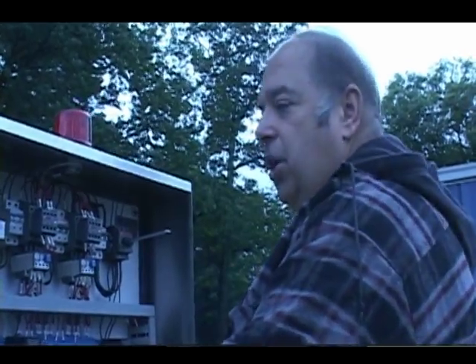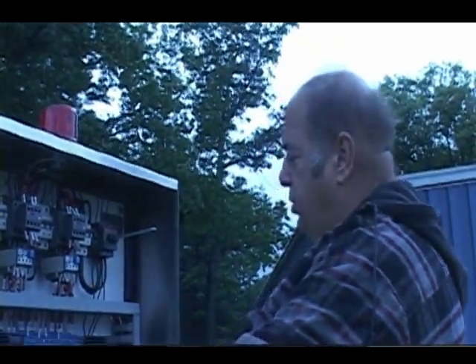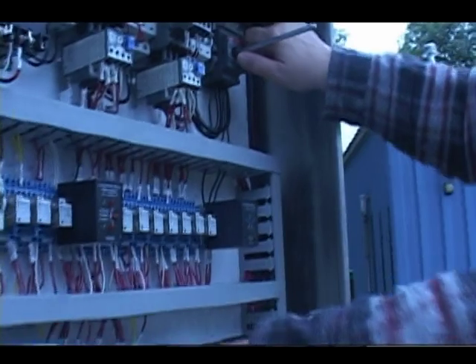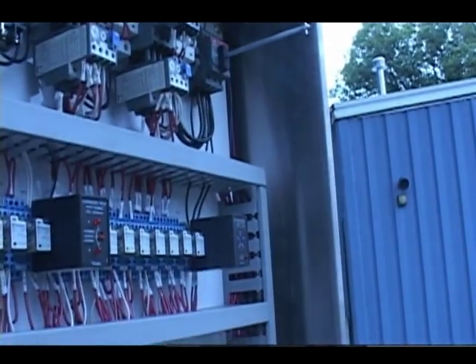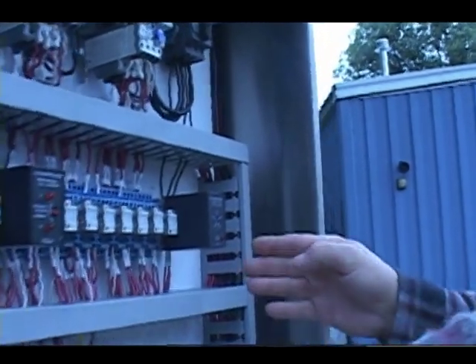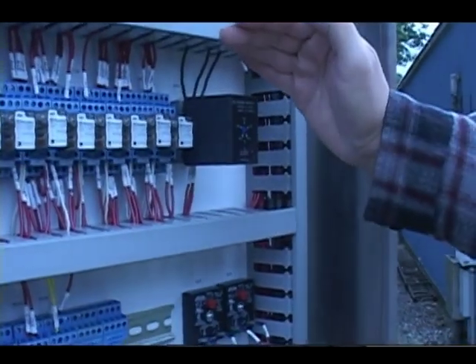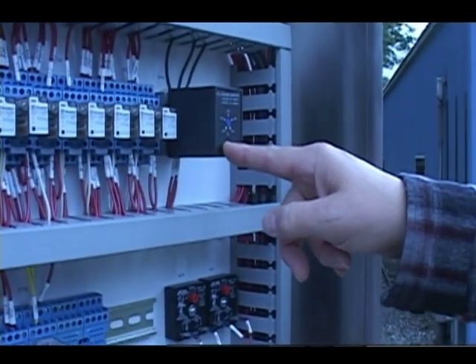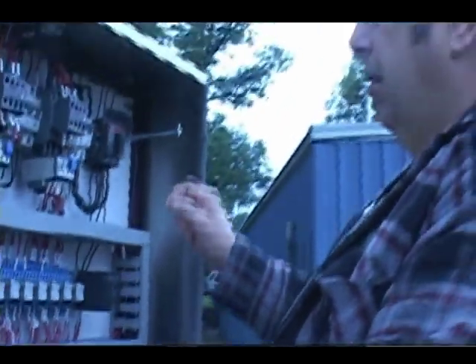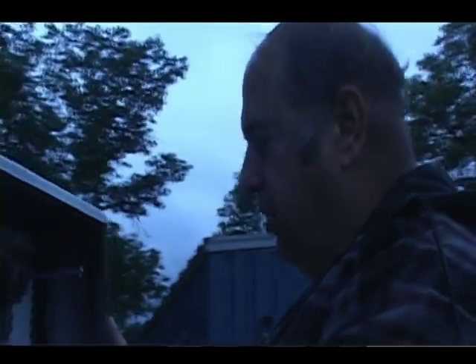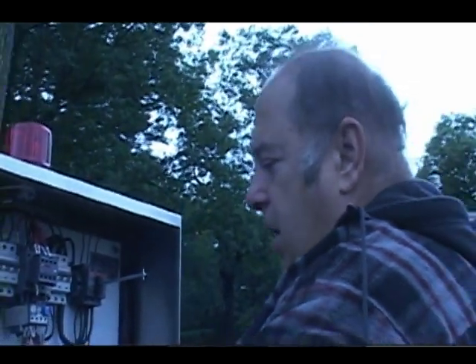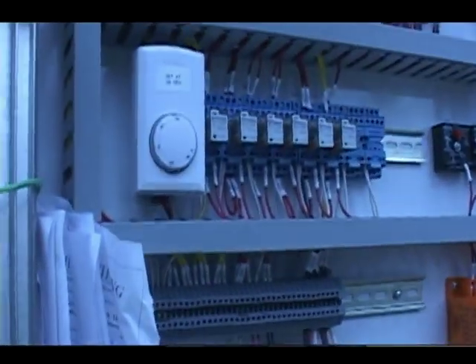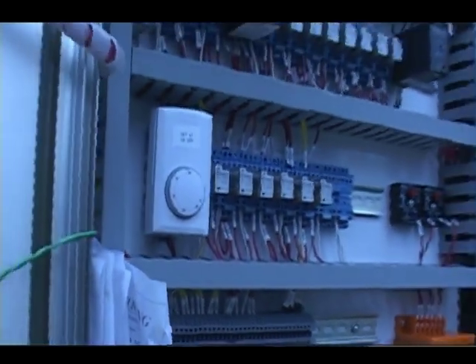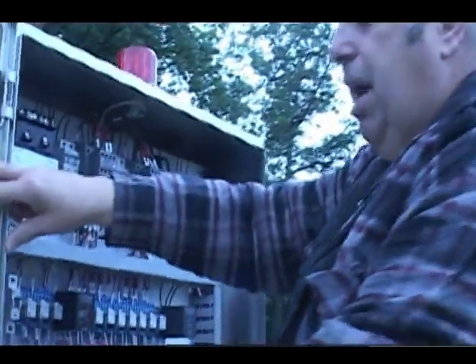Okay? There's also a 3-phase monitor, which is this device. Now, with it on, and you have the correct voltage, you see that there's a little light on. It's difficult to see in the sunlight. That tells you you have the correct voltage. Okay? Now, if you don't, none of the pumps will run. It simply shuts off. Right? Now, we have a thermostat here that we have set for 50 degrees. That's to keep the panel somewhat warm. It's not really an issue in this climate.